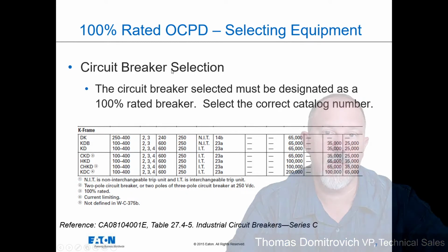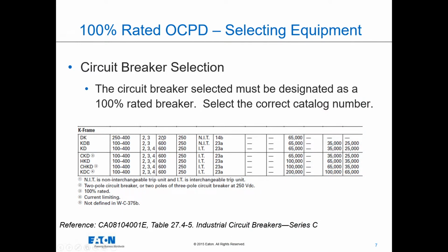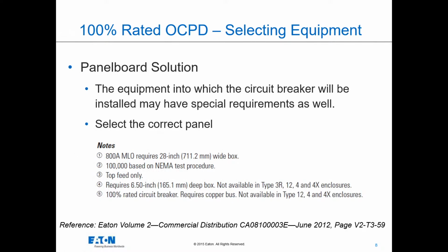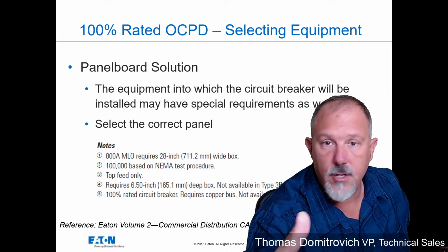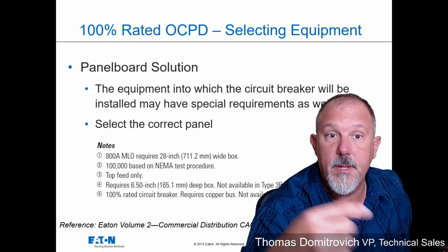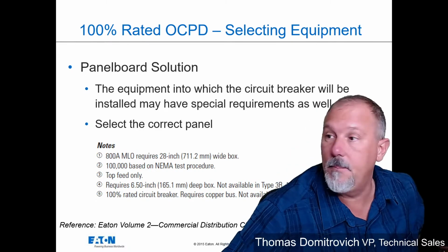And when you look at this, these are out of our catalog. It says my 100% rated breakers are the CKD and the CHKD. So not all of these are 100% rated. This one is a panelboard. What this says is 100% rated circuit breakers require copper bus, not available in type 12, 4, and 4X enclosures. So not every enclosure, not every assembly, is going to be able to handle a 100% rated breaker, because it's got to have copper bus. And it might have to be a special type of copper.